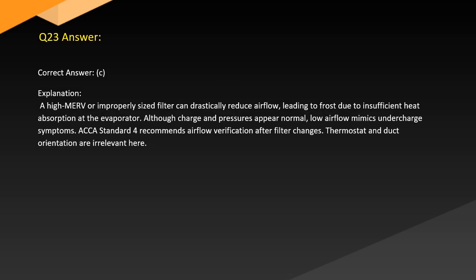Answer. Correct answer, C. Explanation. A high MERV or improperly sized filter can drastically reduce airflow, leading to frost due to insufficient heat absorption at the evaporator. Although charge and pressures appear normal, low airflow mimics undercharge symptoms. ACCA Standard 4 recommends airflow verification after filter changes. Thermostat and duct orientation are irrelevant here.